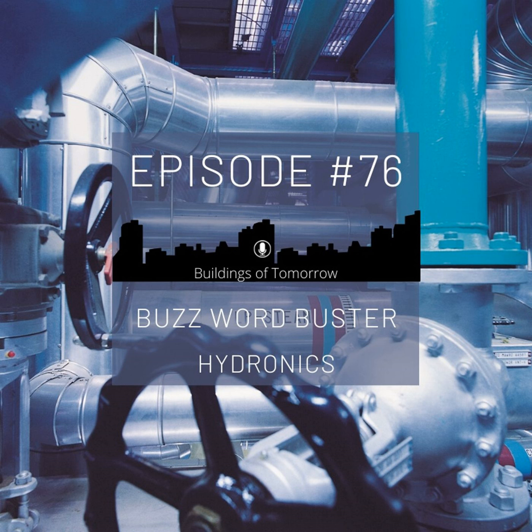Now let's have a look at a couple of key terms or valve characteristics that we might see with a KVS valve, similar to what we did with a pressure-independent valve. V100. Yes. V100. That's a term that you could also apply to a PICV, but it's mainly used with KVS, and it's really the 100% volumetric flow, you could say. And this is derived from the equation that considers the power that we have to provide to a consumer and the decisive temperature difference that is needed at this consumer. And out of that, we can figure out how much water we have to be able to handle with this valve. And that's what's called V100 for this KVS valve.